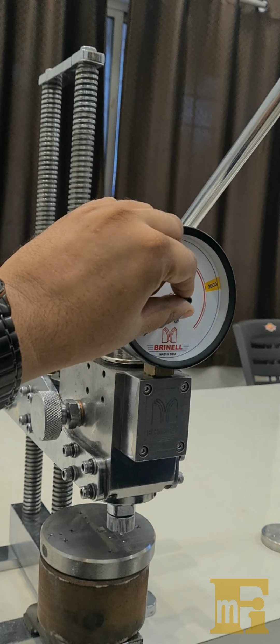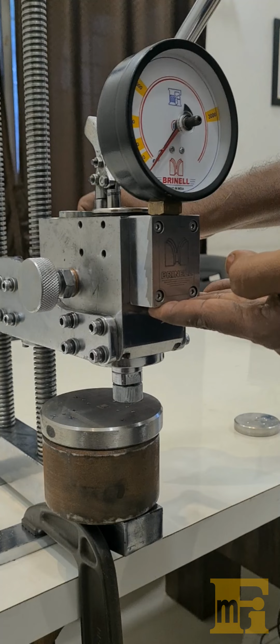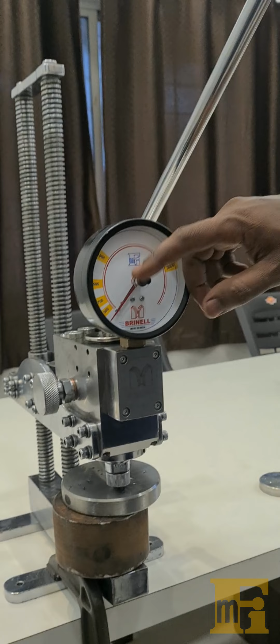Now we will conduct the Brinell 3000 kg load test. First, bring the indenter in contact with the job. Then close the pressure release valve. Then start pumping using the handle. Once the 3000 kg load is achieved, the internal pressure release mechanism will automatically activate and start releasing the pressure, so it will not overshoot 3000 kg load.